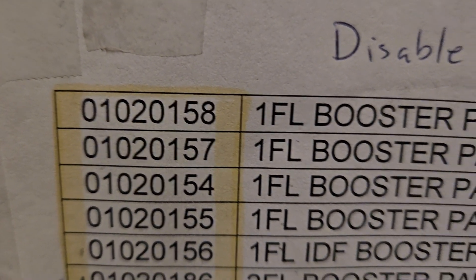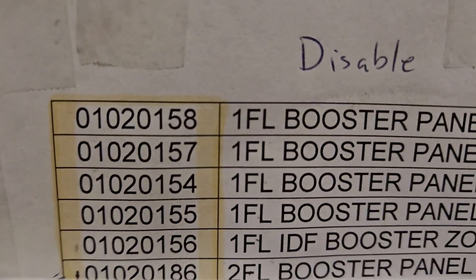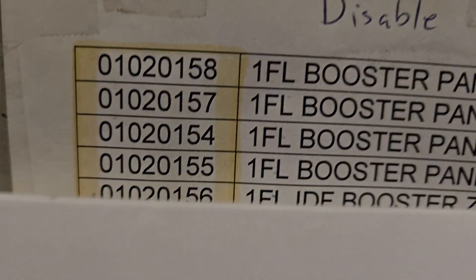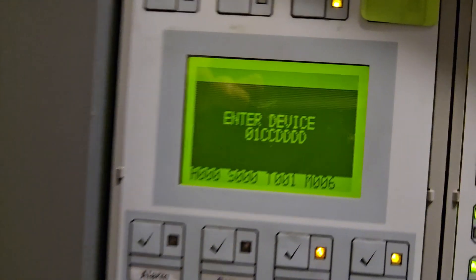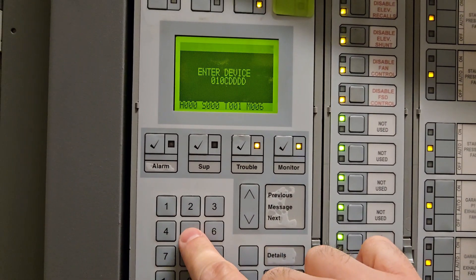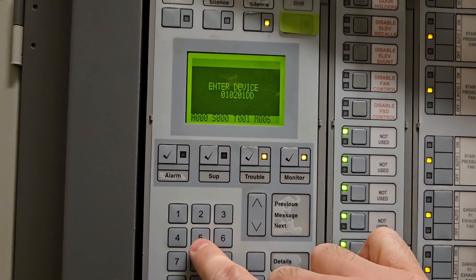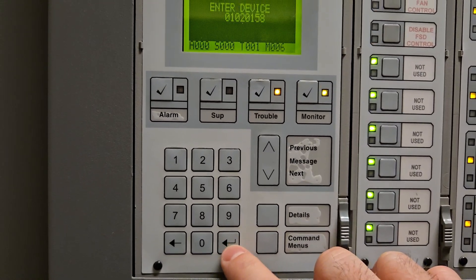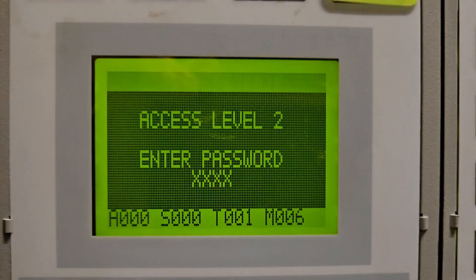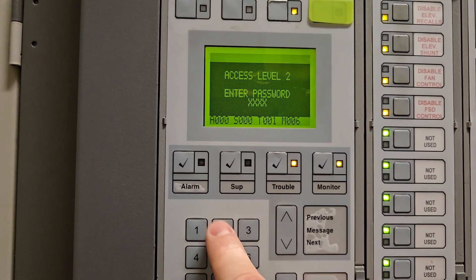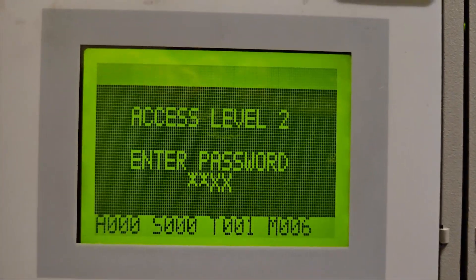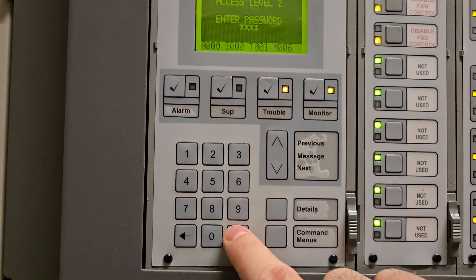So the first one is 01-02-0158 — that's going to be the first floor booster. I already have the zero one; I'm going to put in zero two, zero one, five eight. I'll make sure my number is correct, then I'm going to hit the enter button — this little arrow. It's going to ask me for a password. The access level two password is four twos, so I'm going to hit the number two button four times.